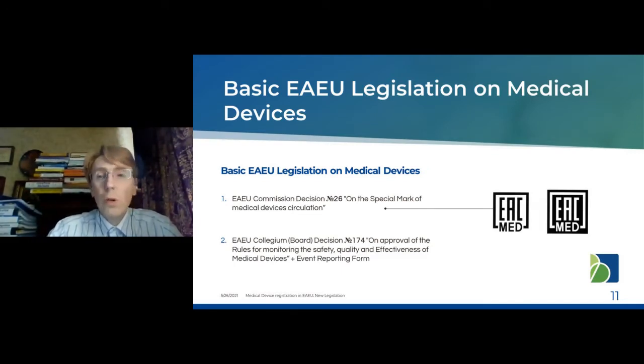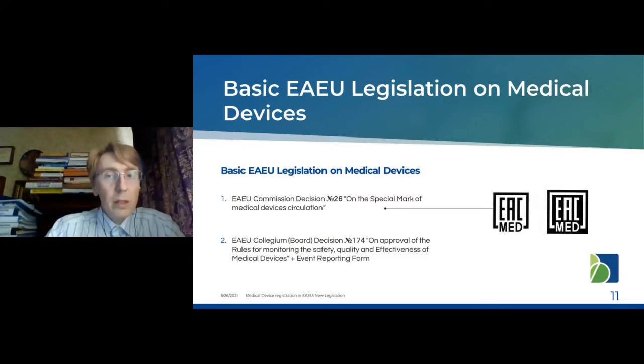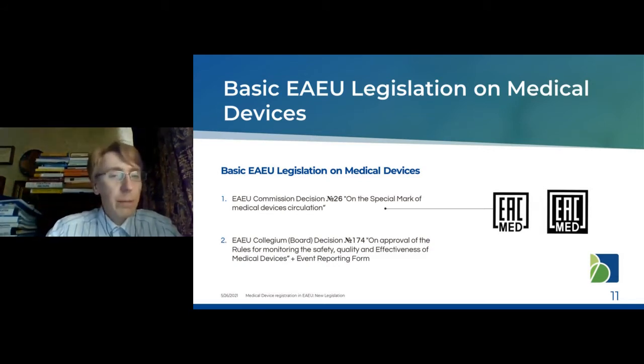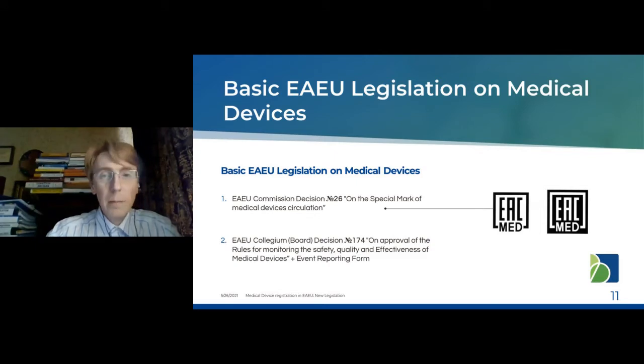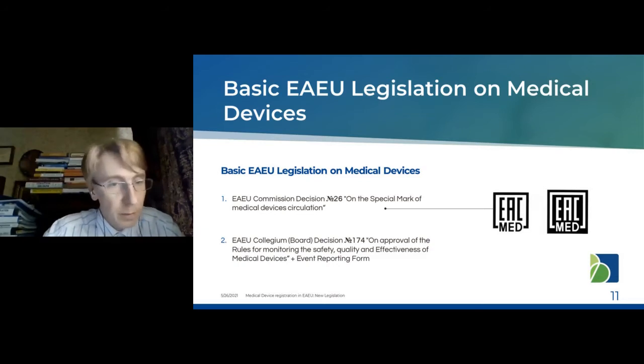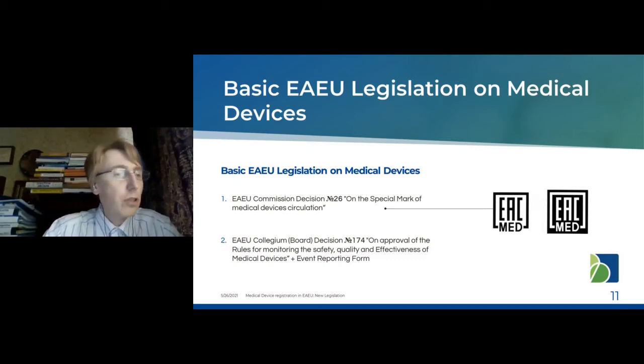Some important documents to highlight separately: Commission Decision Number 26 on the Special Mark of Medical Devices Circulation — all devices registered in the Eurasian Union must bear this mark on their labeling after registration. And Collegium Decision Number 174 on Approval of the Rules for Monitoring the Safety, Quality and Effectiveness of Medical Devices, which includes the event reporting form for post-registration vigilance activities.